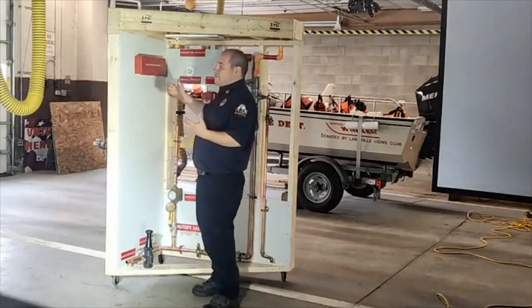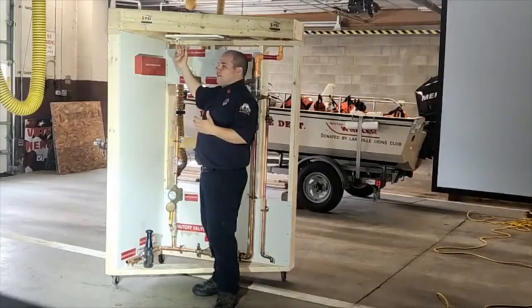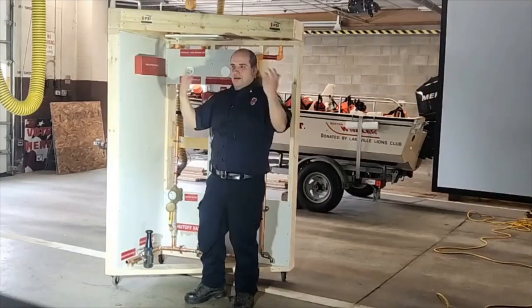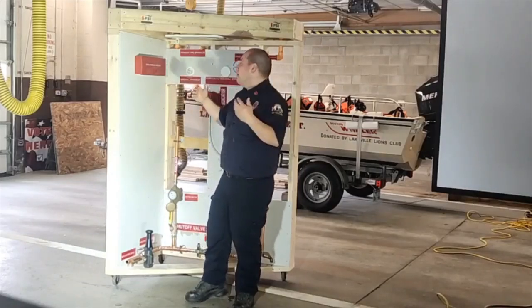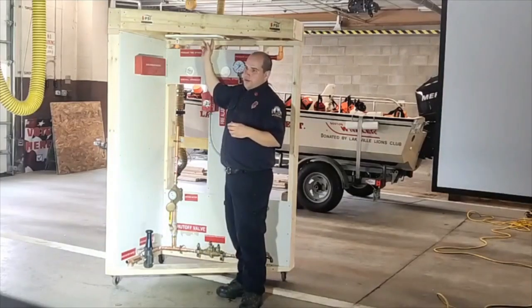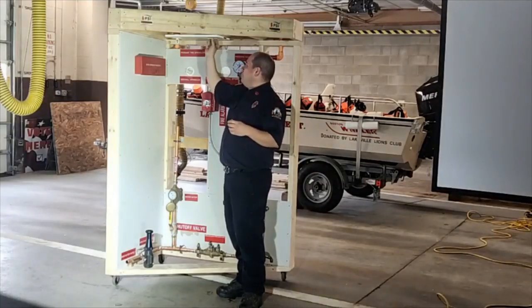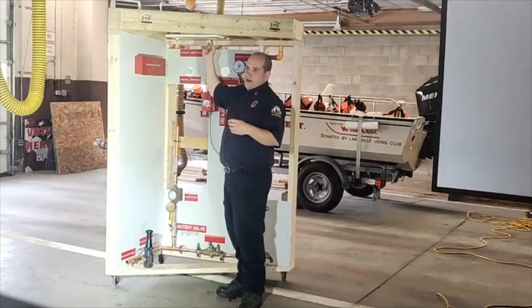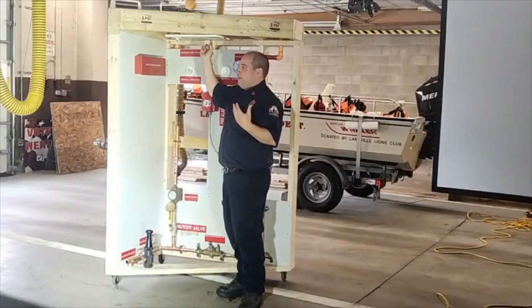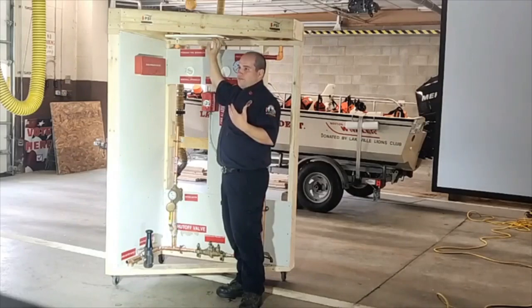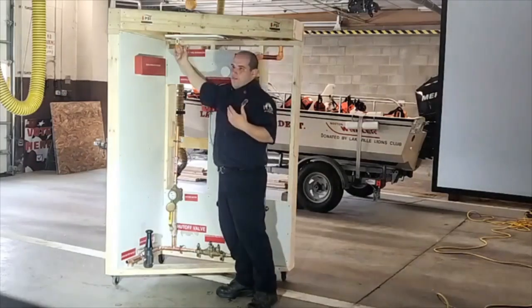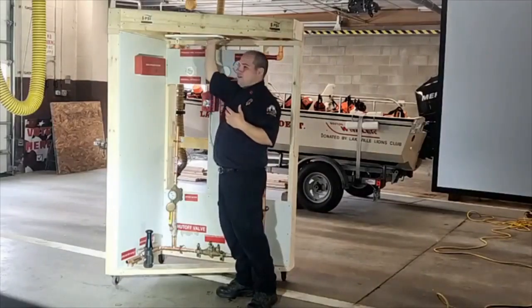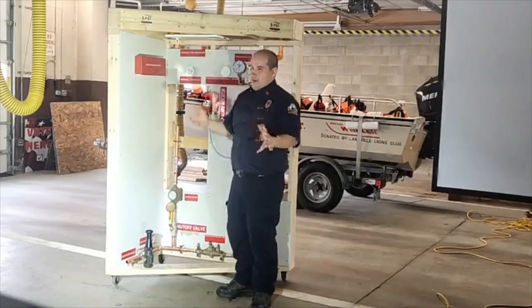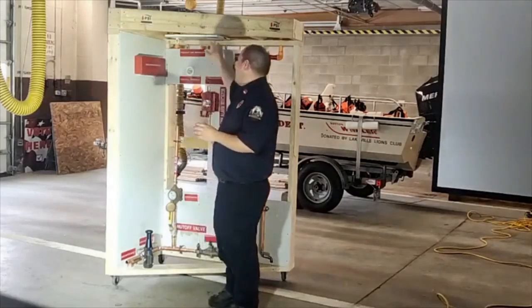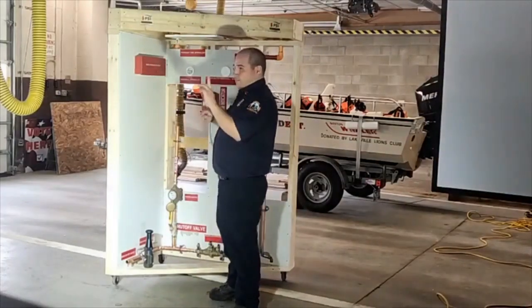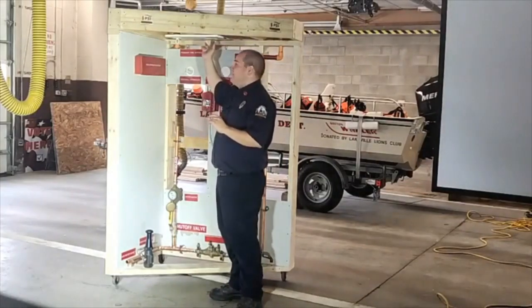One thing people get concerned about with these pendant sprinkler heads is the looks, like not wanting these sprinkler heads coming down through the ceiling. You can get a sealed sprinkler head that has a little plastic cover that can be painted whatever color to match your ceiling. It's the same thing, it'll heat up when exposed to fire and drop down when you need it, but when you don't need it, it stays recessed and covered. So if you're worried about aesthetics or looks, you don't even have to worry about it, they've already thought about it for you. One thing you do have to be careful of if you go with this type is don't paint these over.